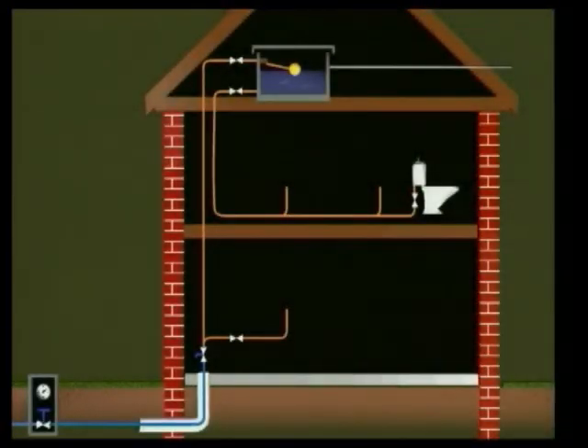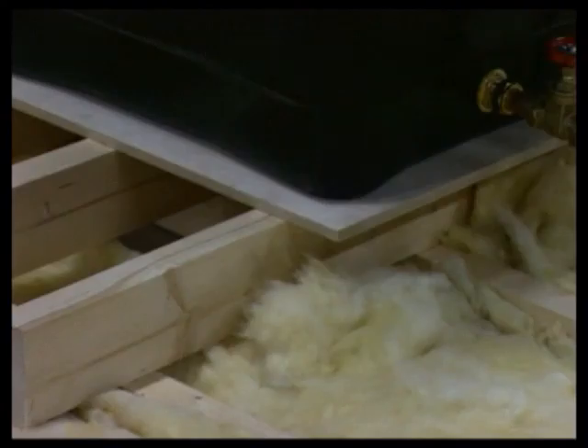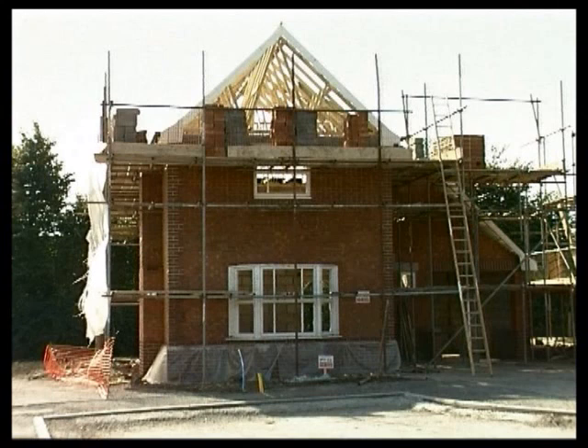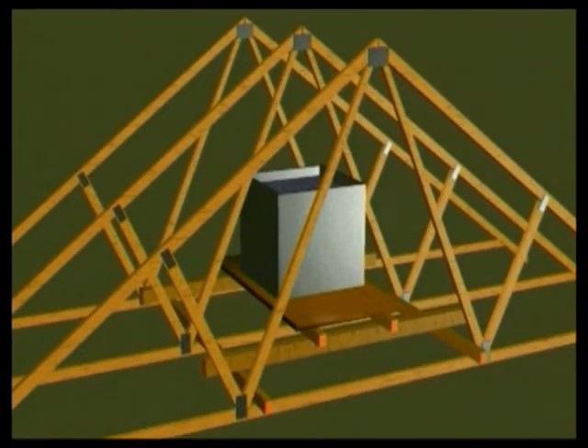Where a continuous water supply can't be guaranteed, drinking water is fed directly, but other fittings are supplied indirectly from a storage tank. Tanks, often referred to as cisterns, are available in a range of sizes and can help even out demands on the main supply. They're supported on softwood boards or sheet materials such as marine ply. Truss rafters are finely engineered and can easily be damaged by incorrect loading. Tanks of up to 230 litres can be supported on three trusses. Bearers running across the trusses should be located at the node points. Additional bearers support the deck.